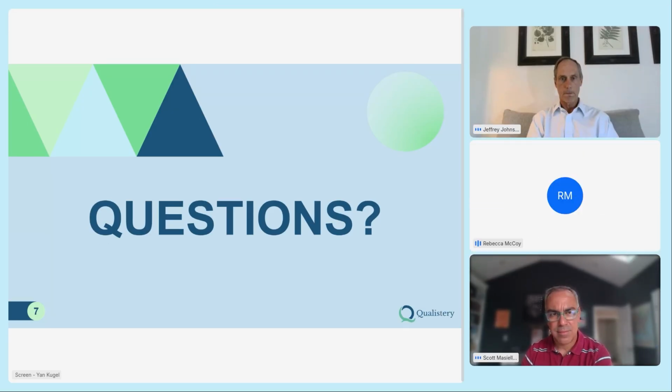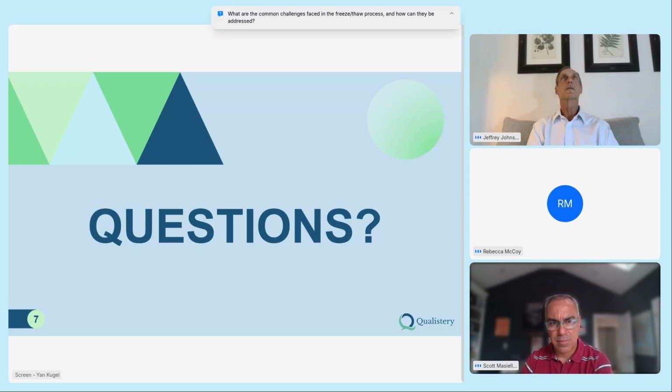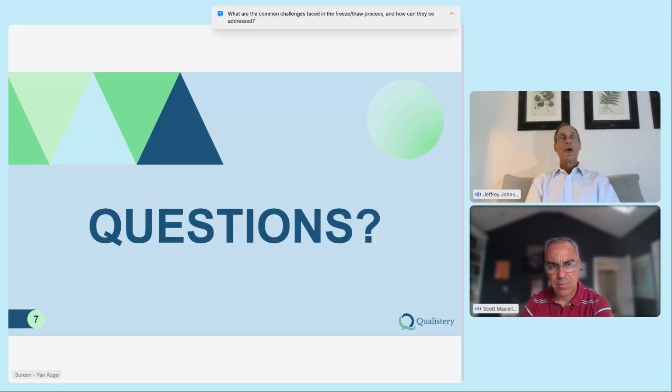All right, fast follow. What are the common challenges faced in the freeze thaw process, and how can they be addressed? I spent a lot of time designing, building, and running biotech factories, and focusing on drug substance freezing. Integrity is the biggest one, which is why I said taking the shell and opening it is not a great solution, because you're opening a shell of a -80 bag, and you want to minimize all handling at -80 because they're brittle.